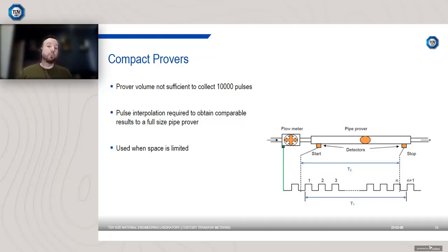Now, the advantage of compact provers is they're used when space is limited, so they've got a much smaller footprint than conventional provers. So there are ISO standards that go into more detail about pulse interpolation. So ISO 7278 Part 3 talks about all the various pulse interpolation techniques. It's typically handled by a dedicated flow computer, and it's important to note as well that even with conventional provers, there might still be an issue with collecting 10,000 pulses if the meter that you're trying to prove outputs a particularly low frequency. So pulse interpolation can still be used with quite large provers as well.